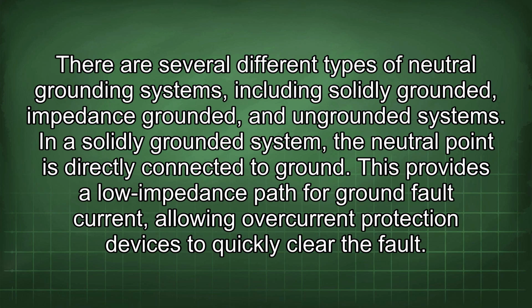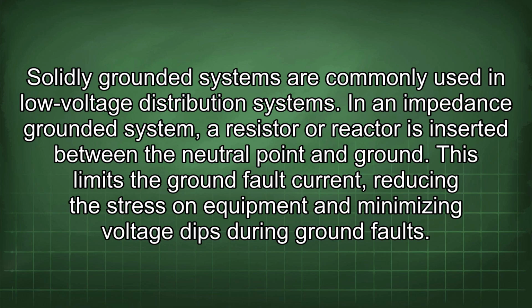In a solidly grounded system, the neutral point is directly connected to ground. This provides a low impedance path for ground fault current, allowing overcurrent protection devices to quickly clear the fault. Solidly grounded systems are commonly used in low voltage distribution systems. In an impedance grounded system, a resistor or reactor is inserted between the neutral point and ground. This limits the ground fault current, reducing the stress on equipment and minimizing voltage dips during ground faults.